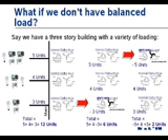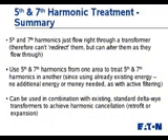There are better ways to go about it, and application engineers are available to help with your designs. To summarize our treatment of fifth and seventh harmonics: fifth and seventh harmonics flow right through a transformer, so we can't redirect them as we do with triplen harmonics, but we can alter them as they flow through using phase shifting. We use fifth and seventh harmonic energy from one area to treat fifth and seventh harmonic in another area. Since this is already existing energy in the building, no additional energy or money is needed as with active filtering — which consumes additional current to create anti-harmonics. What we're doing through the transformer magnetics is phase shifting those currents to treat currents in other areas. This means you can introduce the HMT-NON (zero-degree) in combination with existing standard delta-Y transformers to achieve harmonic cancellation, making HMTs suitable for retrofit or expansion projects with great impact on harmonic distortion.